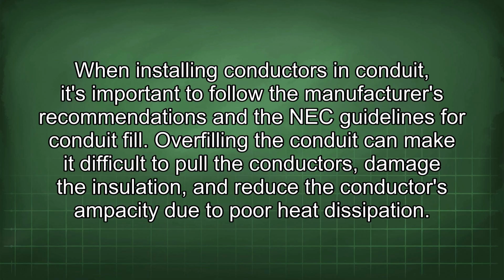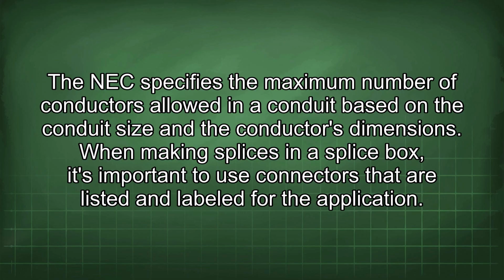When installing conductors in conduit, it's important to follow the manufacturer's recommendations and the NEC guidelines for conduit fill. Overfilling the conduit can make it difficult to pull the conductors, damage the insulation, and reduce the conductor's ampacity due to poor heat dissipation. The NEC specifies the maximum number of conductors allowed in a conduit based on the conduit size and the conductor's dimensions.